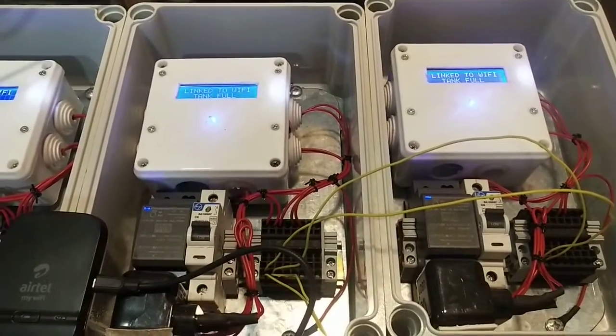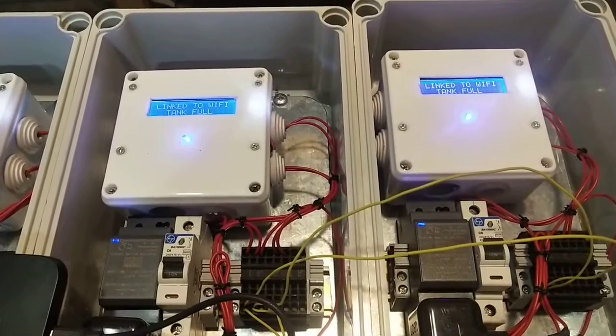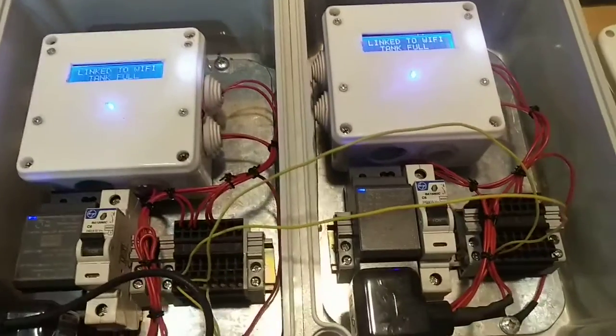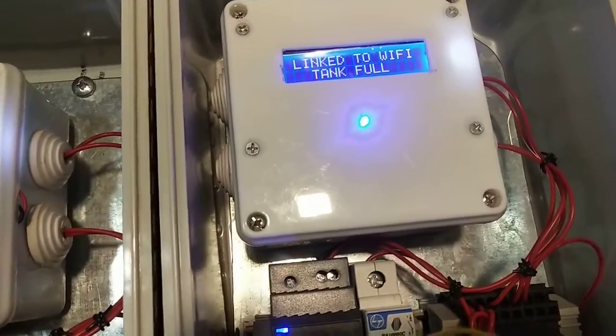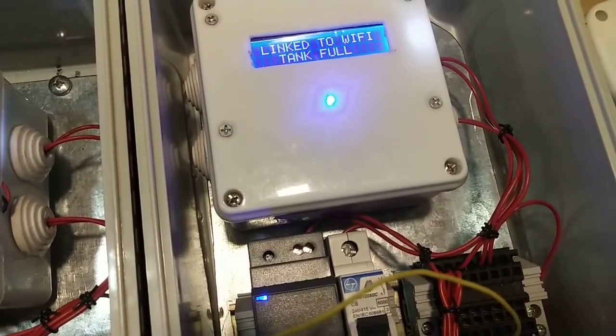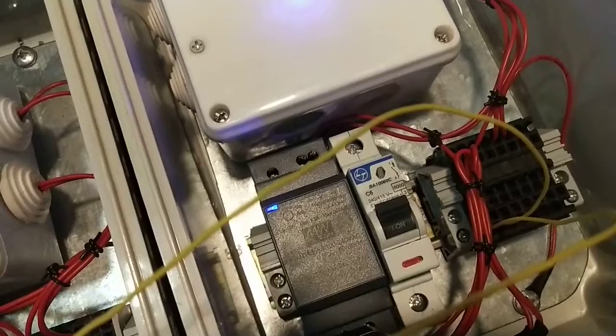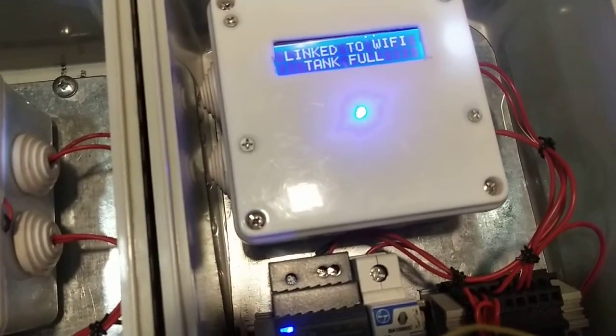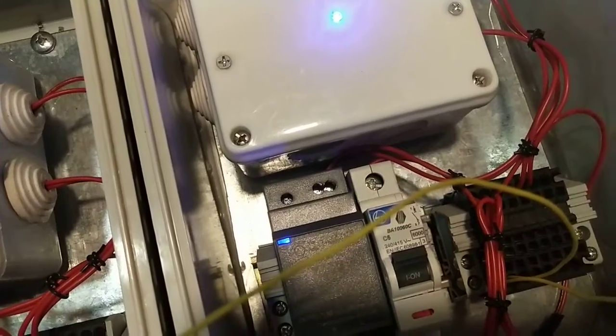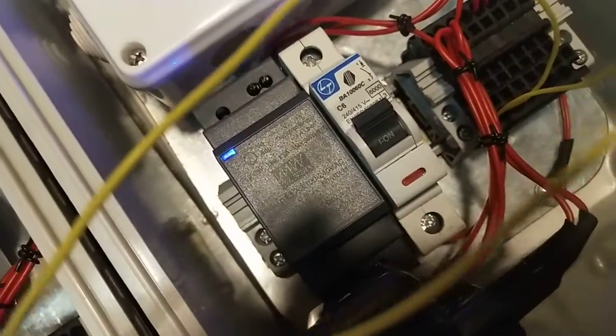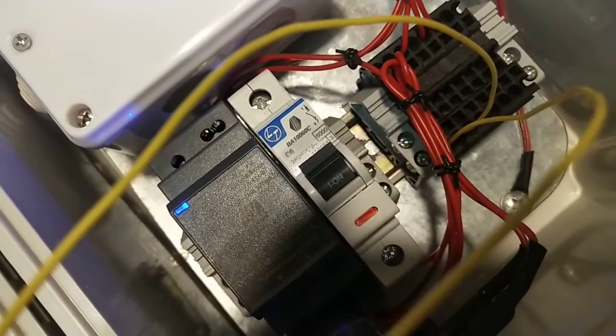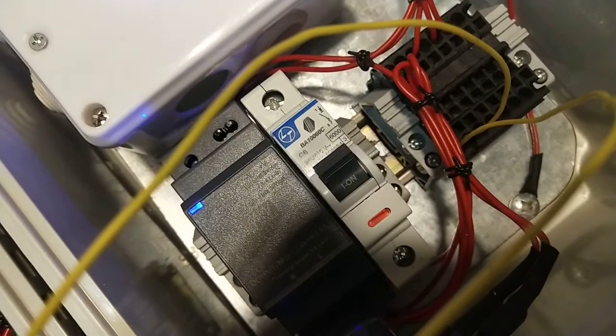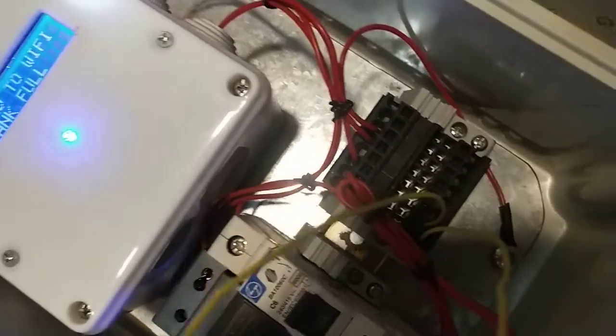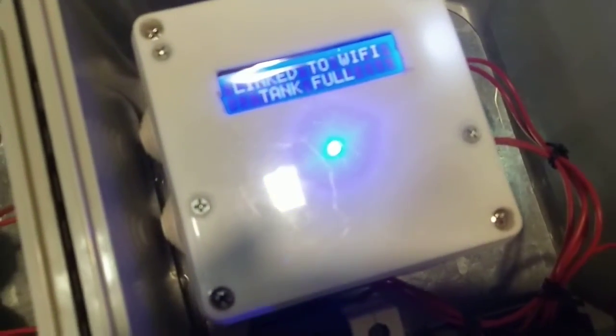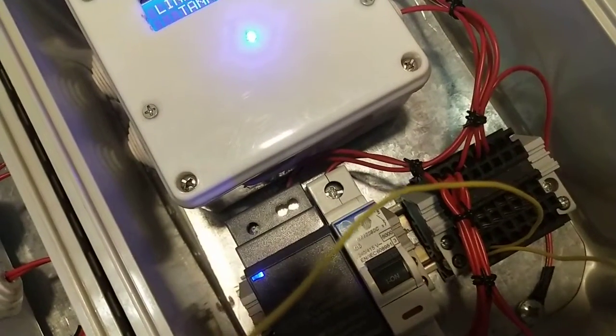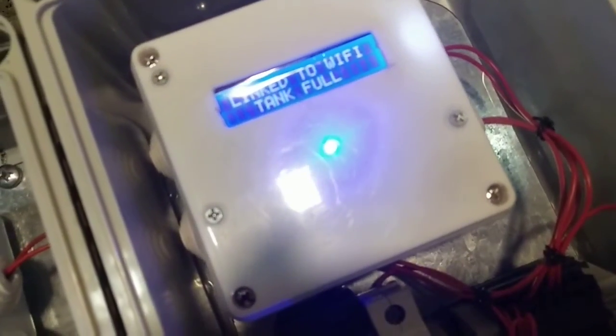Here, as you can see, the 3 units are ready. Each of the units has an IoT U-link which is connected to an SMPS. The U-link has a 24-volt power supply built in, so that power supply is being energized by this SMPS unit. It has an MCB on the live side for protection, and this particular U-link has an NC contact which stops the pump in case it is about to overflow.